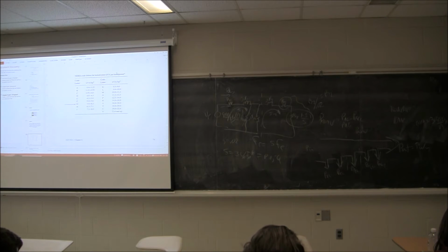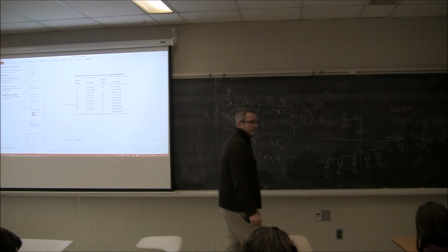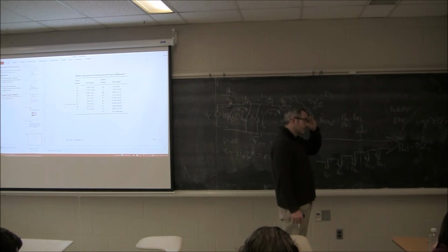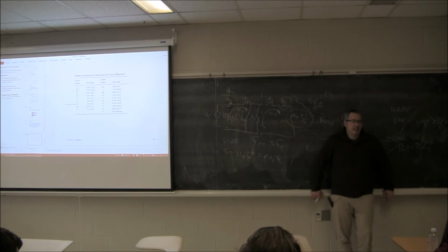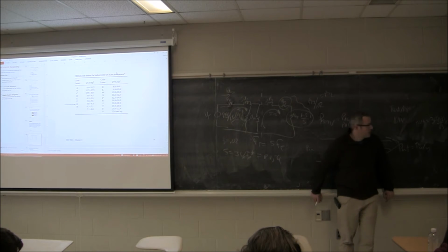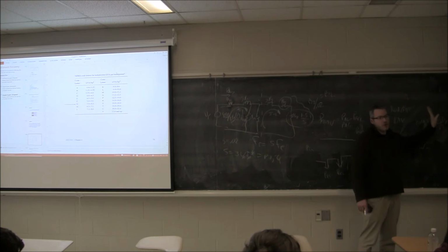Joe? So I have a question, and hopefully I'm not beating a dead horse, but for your kVA, you have 480 divided by the square root of 3, and then you have that multiplied by 3. Yep. So the 277, that's your voltage for one phase? Yes. It's a Y-connected motor, isn't it? Okay. So you wouldn't multiply it by 3 if it was delta? No, because this current we'd be calculating here would be a phase current too, right? Okay. So usually you just multiply the single phase by the single phase, and you always multiply by 3.